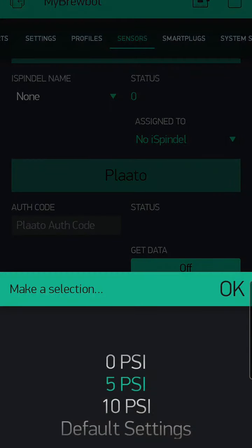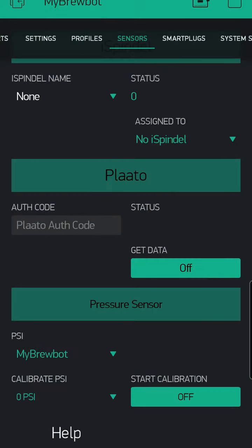Repeat the process for 0 psi with all pressure released. The calibration settings will be saved to the controller. Note: it is important to calibrate at all 3 pressure settings. Failure to do so will result in inaccurate results.